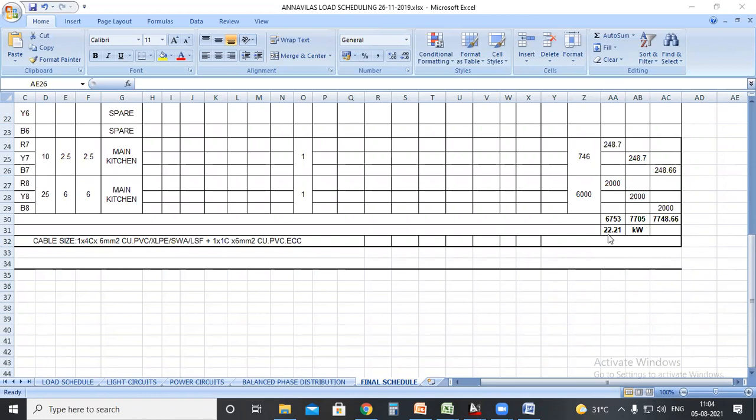Here we got a value of 38. So we will obviously be checking the catalog for the circuit breaker and MCCB. MCCB 63 ampere is not mandatory here because it does not have that much load initially anyway. MCCB means the cost will be high. The total load is coming around 38 ampere, right?